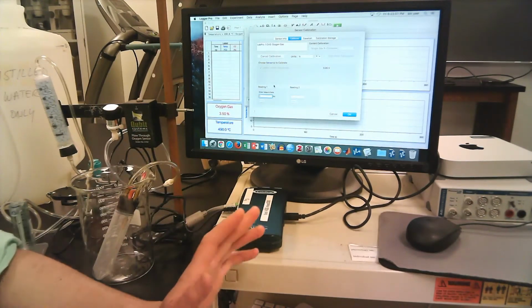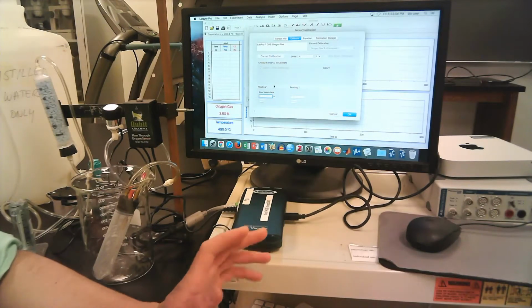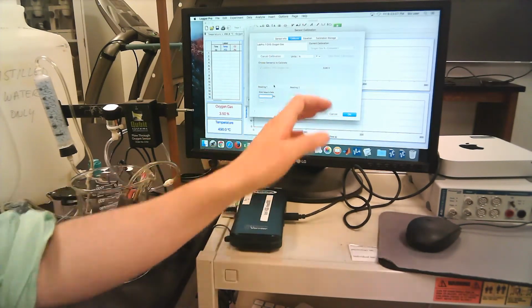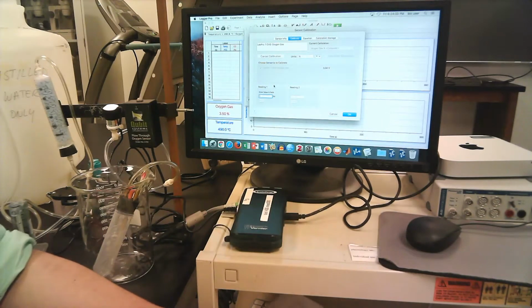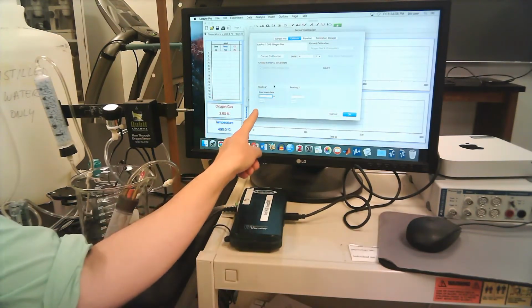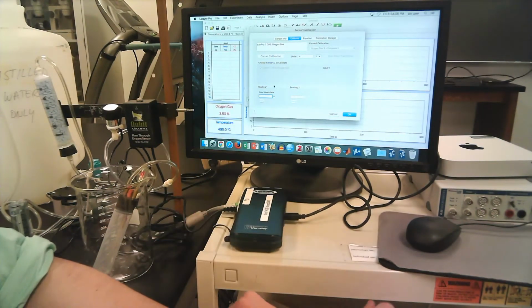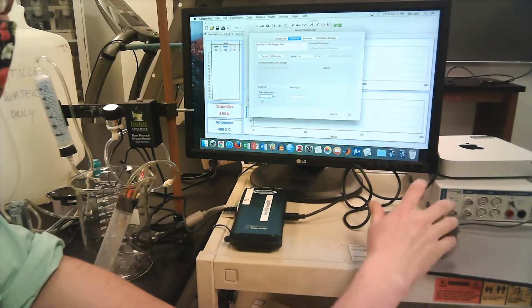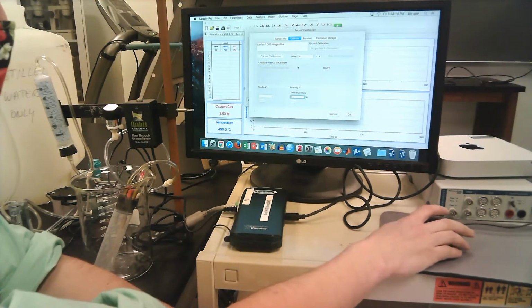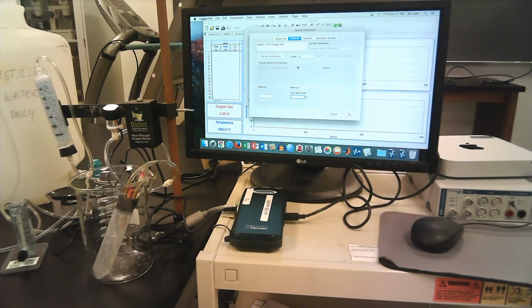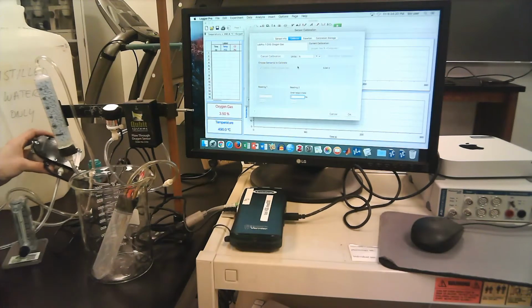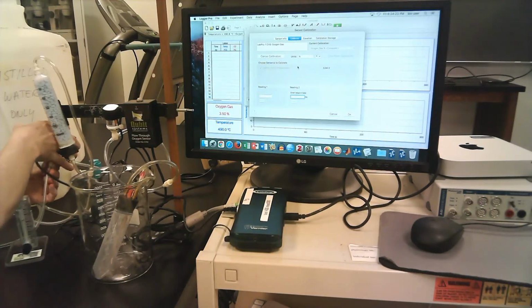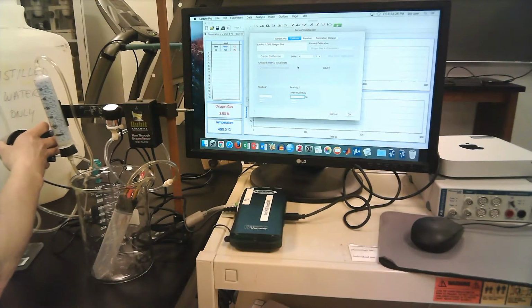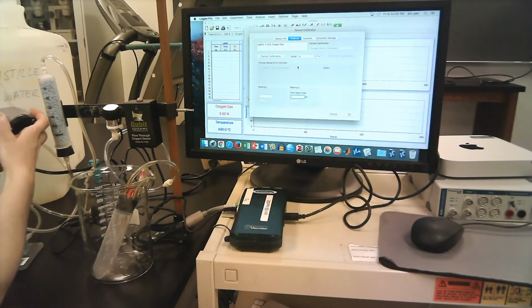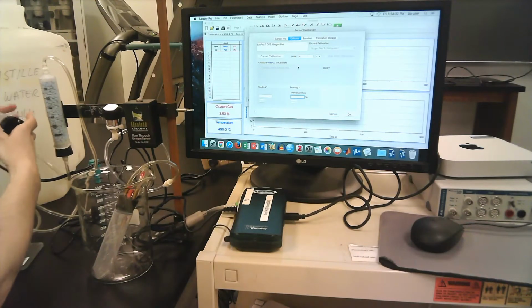All right, so for the sake of instruction, let's say we've reached that low stable reading. And at this point, since we're just flowing nitrogen gas through, we're working with 0% oxygen. So where this says reading number 1, I'm just going to type in 0. And then I'm going to click this keep button. All right. Then I'm going to unplug my nitrogen bag, and then I'm going to plug in the room air tubing, okay?